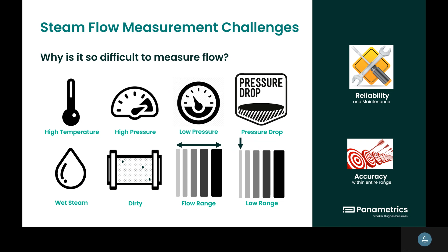So for ultrasonics, we'll cover how it resolves a lot of these issues. First, the ultrasonic can handle high temperatures, can go from 100 to 450 degrees Celsius in steam measurements. So it has that rangeability. We have two different types of technology we use, both ultrasonics, and we'll cover them a little bit later, but we can handle that temperature overall. Pressure, we can handle anywhere from 150-pound flange class to 2,500-pound flange classes. So we can handle that rangeability.